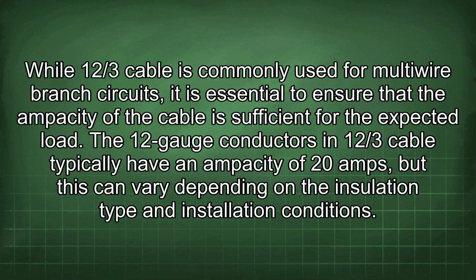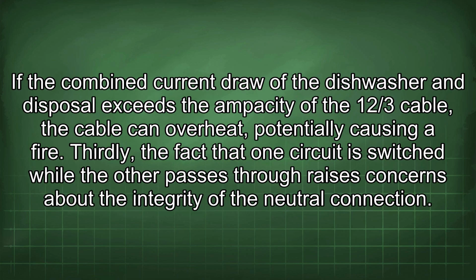Secondly, the use of 12/3 cable introduces another potential issue. While 12/3 cable is commonly used for multi-wire branch circuits, it is essential to ensure that the ampacity of the cable is sufficient for the expected load. The 12-gauge conductors in 12/3 cable typically have an ampacity of 20 amps, but this can vary depending on the insulation type and installation conditions. If the combined current draw of the dishwasher and disposal exceeds the ampacity of the 12/3 cable, the cable can overheat, potentially causing a fire.